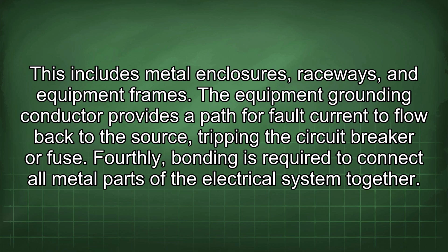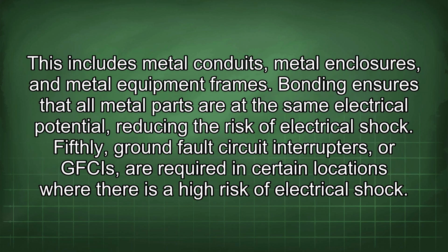The equipment grounding conductor provides a path for fault current to flow back to the source, tripping the circuit breaker or fuse. Fourthly, bonding is required to connect all metal parts of the electrical system together. This includes metal conduits, metal enclosures, and metal equipment frames. Bonding ensures that all metal parts are at the same electrical potential, reducing the risk of electrical shock.